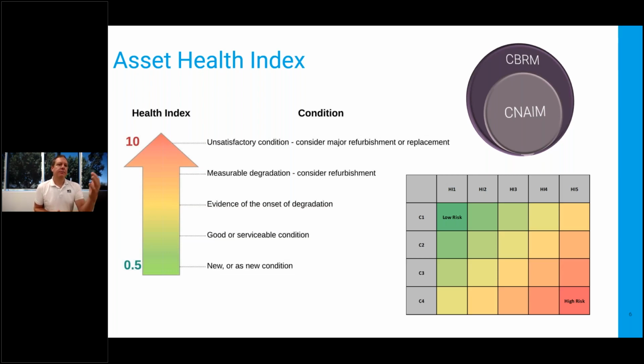You can see some descriptive terms about what that looks like. In the green zone, 0 to 4, assets are in good or serviceable condition, close to new or as new. As they get into the end-of-expected-life period, there's evidence of the onset of degradation. As they get further out into the end-of-asset-life area, with a health index of 7 and above, you see measurable degradation, and you should be considering refurbishment or replacement of the asset.